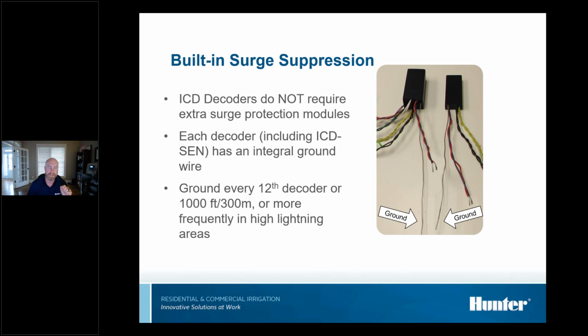One thing ICD decoders have is built-in surge suppression, so we don't require extra surge modules or a dedicated surge module. Every ICD comes with this blank copper ground lead. When we talk about grounding next week or in 2 weeks, we'll cover how to ground this off the decoder - you don't have to buy any extra parts or a surge mod. Our general rule is to ground every 12th decoder or every 1,000 feet, or more frequently.